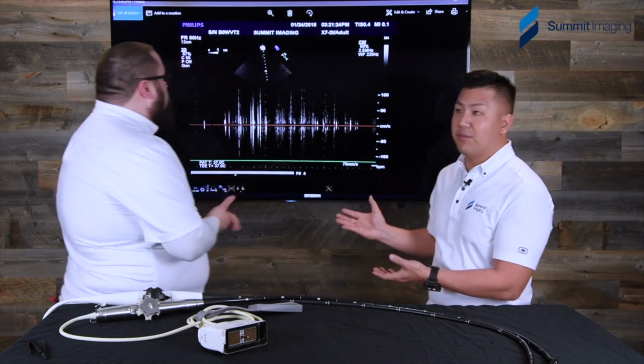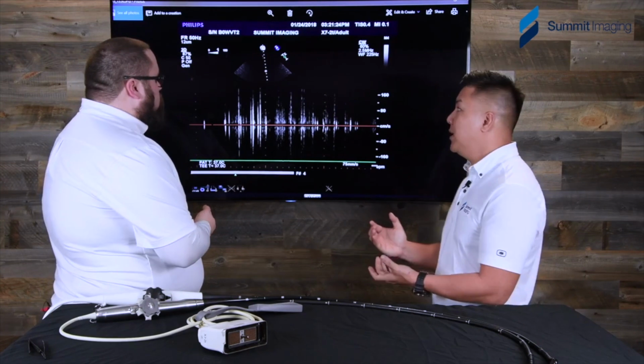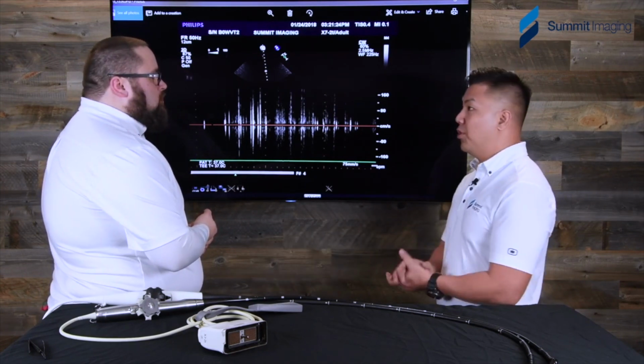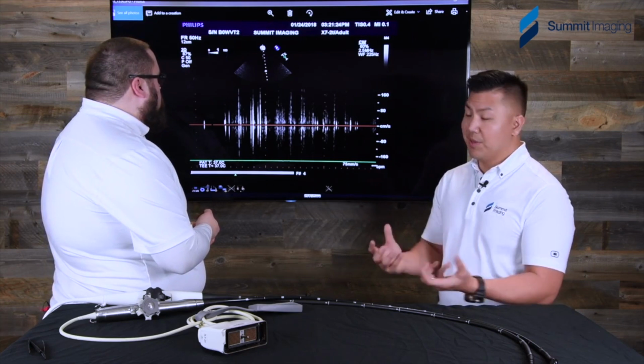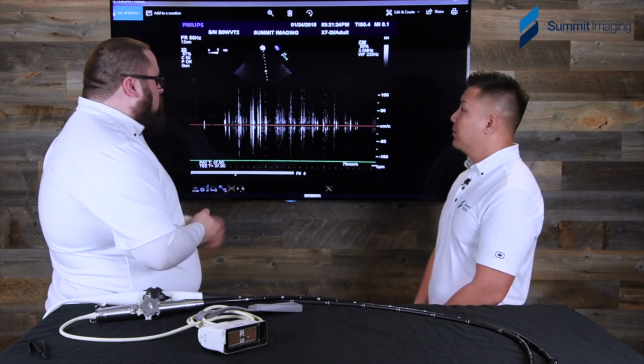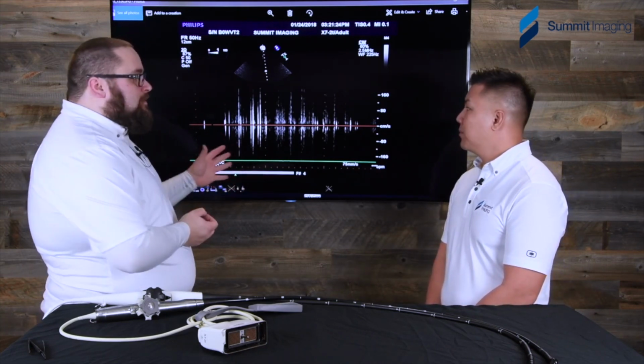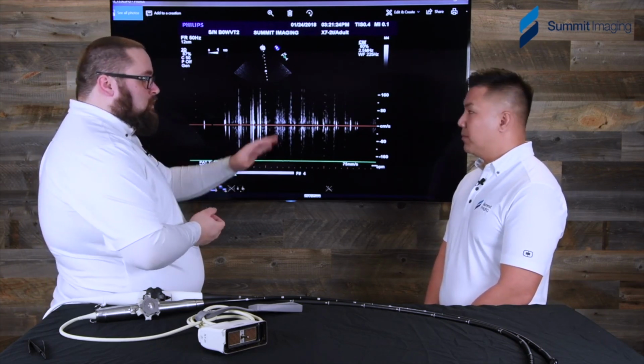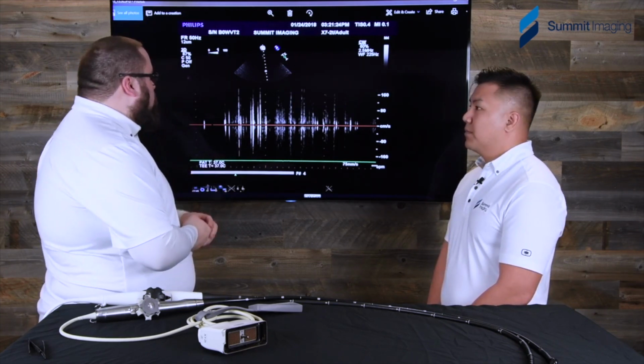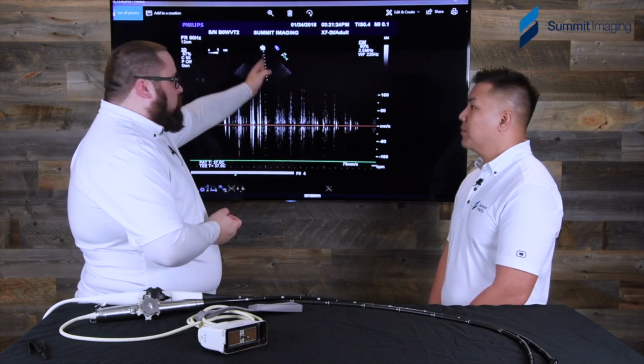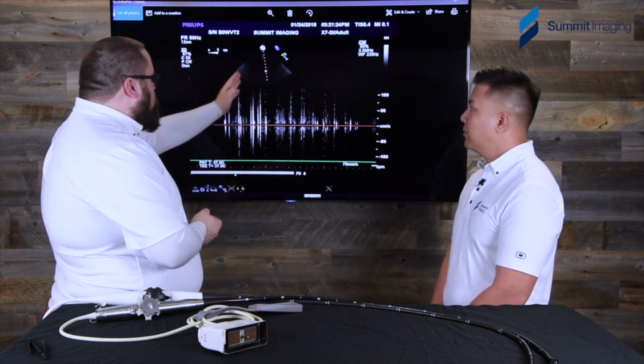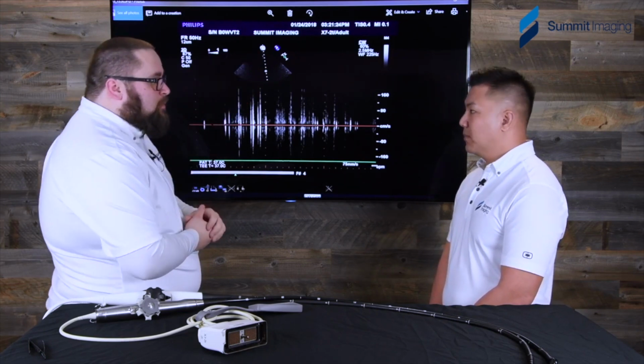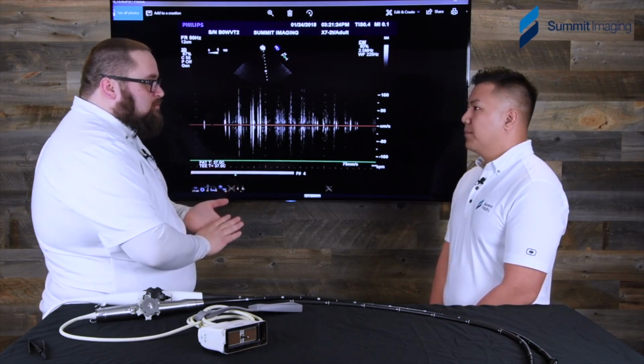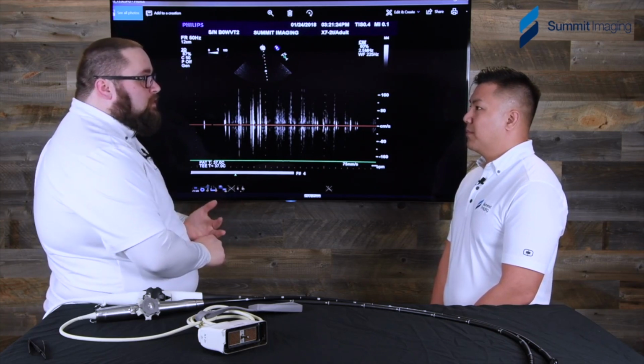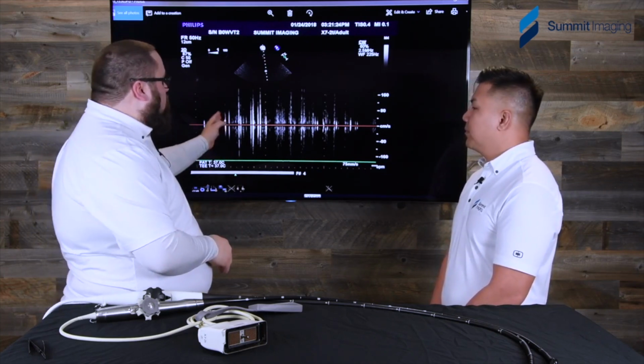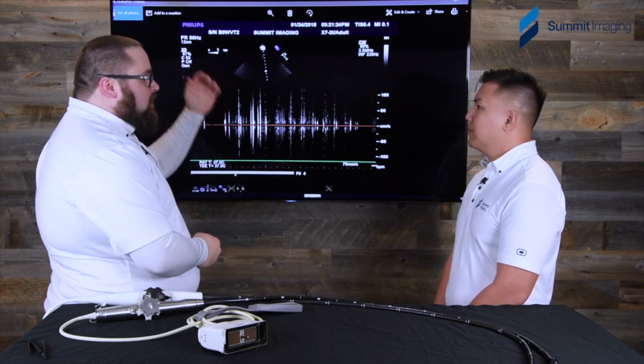Probably the most common symptom and failure that we see as a precursor to the rest of the probe kind of absorbing all that liquid and damaging itself even more. Well, and this wouldn't be reported quickly. CW noise is what we're kind of experiencing here, and it's probably happening only in a certain area of the array. If you move to the left or right, it might actually clear up. But what that's telling me is you have fluid sitting on some lines, or worse, they've actually started corroding and they're touching, and you're getting some chatter, some static, just as it scans into the air.